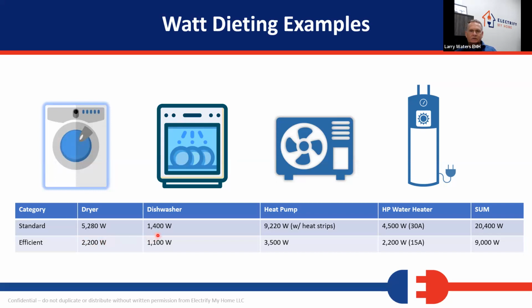If I use an energy efficient dishwasher over a standard dishwasher, I'm using 300 less watts here. My heat pump, a traditional heat pump with heat strips that are being installed every day, everywhere, those systems can use 9,220 watts when that heat pump is running and the heater strip kicks in. That's a ton of power that you have to account for in the system.